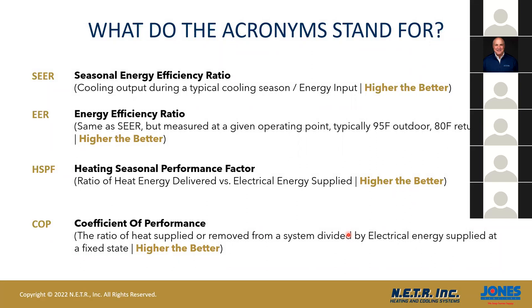All right, the HSPF. This is what is involved on the heating side. When you start looking at the heating side of these systems, again, the higher the number, the better. It's the ratio of heat energy delivered versus the energy supplied. It's a very, very important number with HSPF because you can have certain heat pumps with a low EER and a low SEER. Again, they're going to be less to purchase, but when you purchase it, just be prepared. It's going to cost you more to operate, okay?